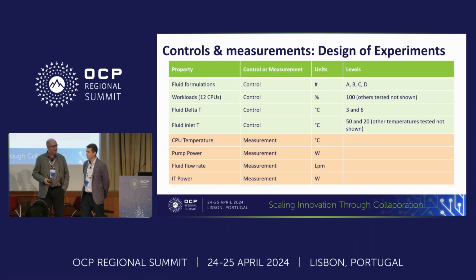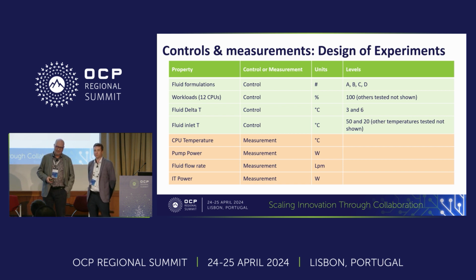So in the setup of the experiment, it's really important that, working with John and the team, we created an experiment which is fair, open and fair. So in doing that, we put 4 fluids up for testing. We defined the controls over that, the workloads, the fluid delta T, the difference between the fluid inlet and outlet temperature, which is controlled, and defined the measurement outputs as well. So making sure that we're recording the CPU temperature, pump power, fluid flow rate, and IT power consumption as well. And in doing all of this, we've come up with a fair test to make sure that every fluid is tested exactly the same. And I think the next slide goes on to start talking about some results, John.